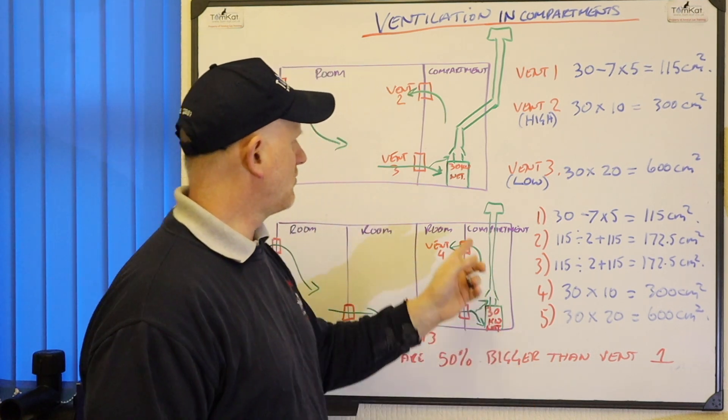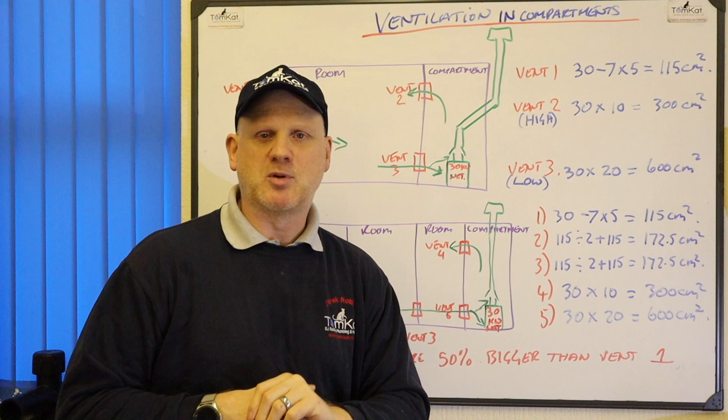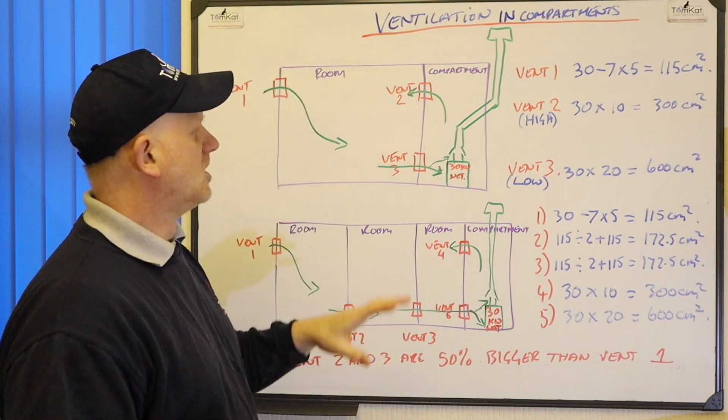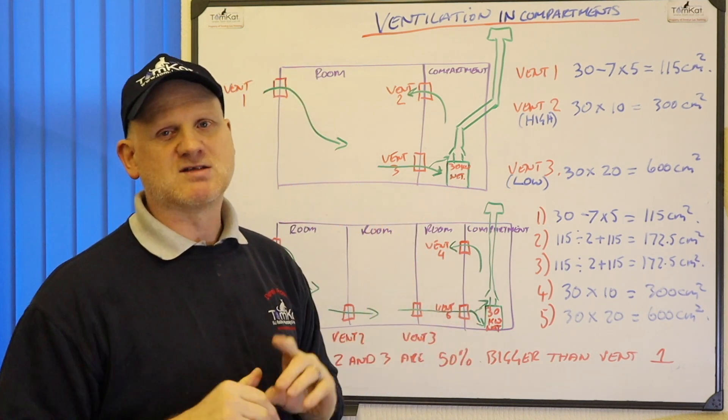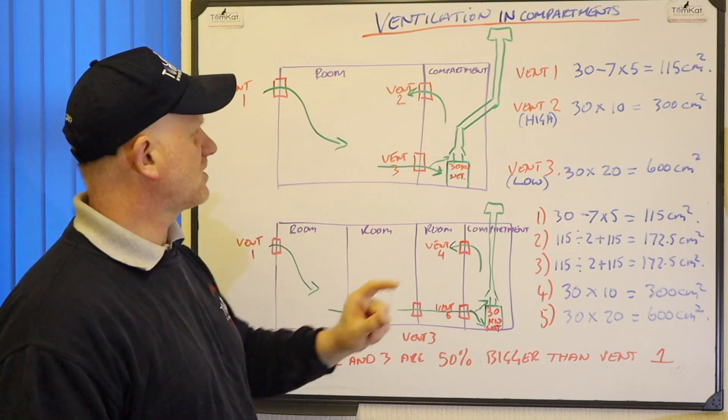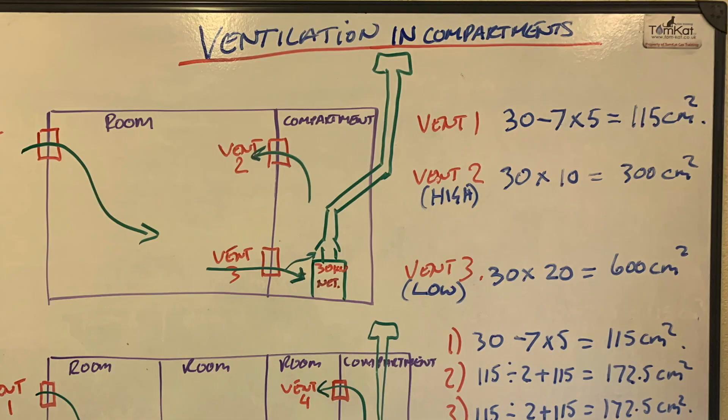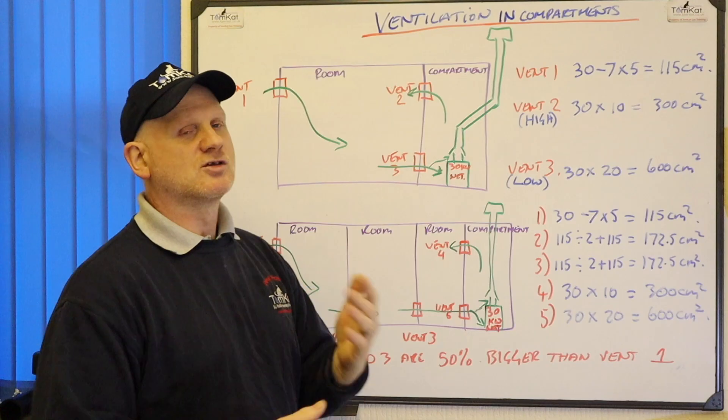So again we've got our 30kW net boiler installed in this compartment so we require three vents. So the vent outside, vent number one is our normal vent. So it's 30 minus 7 times 5 is 115cm². So that's normal.